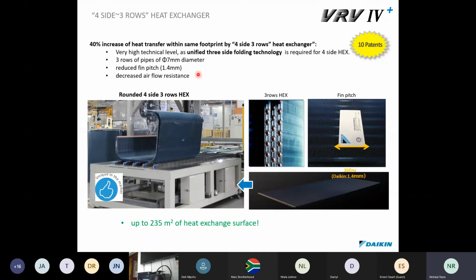So obviously we've got the four-side heat exchanger. That's 1, 2, 3, and 4, right? So maximum surface area would obviously give you better heat transfer, or a footprint for heat transfer. You've got 3 rows of the heat exchanger itself. That's where your copper tubes run through and join in with your fins.